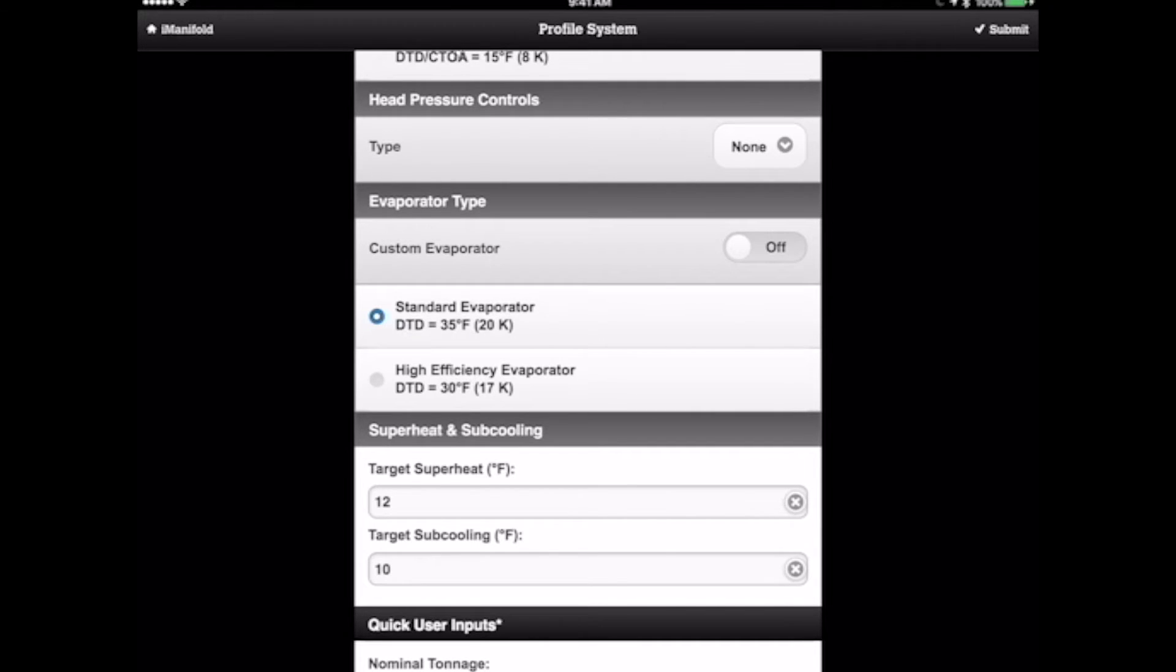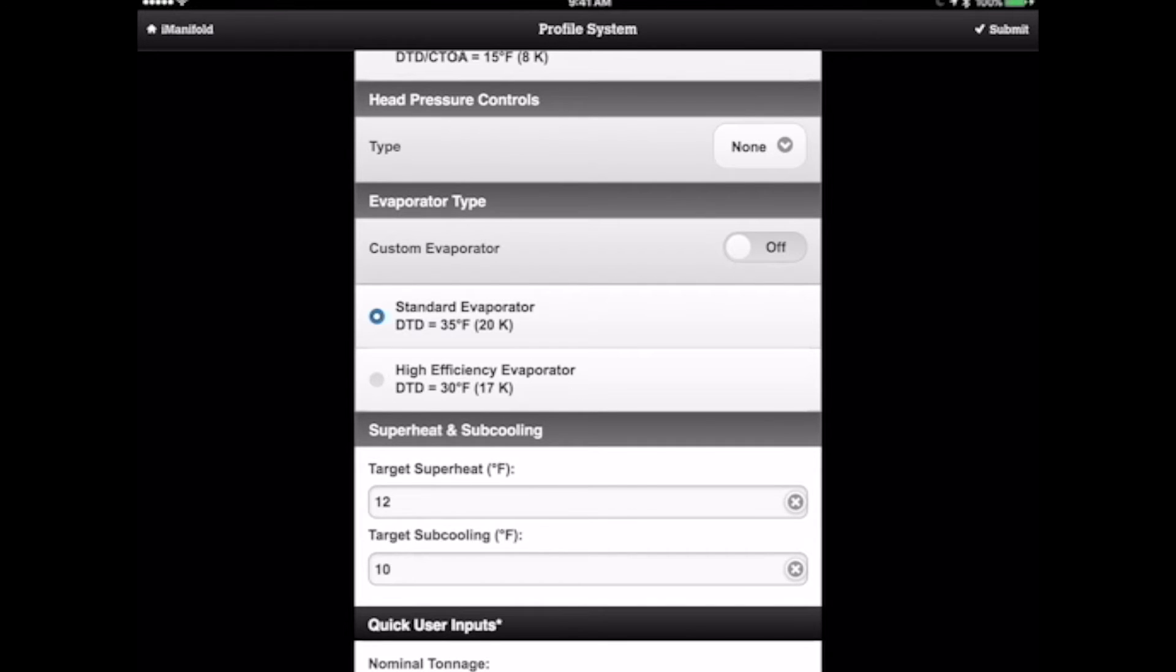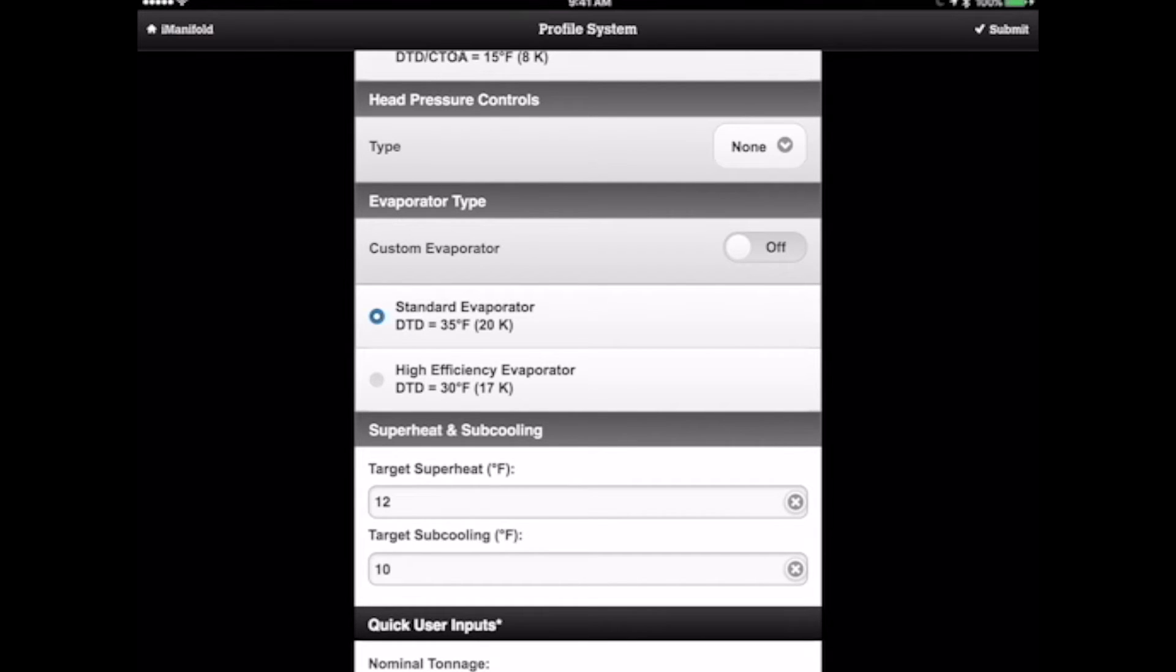The reason we know it's standard efficiency is because it's a matched system. In other words, the condenser and the air handler are matched tonnage wise - two ton condenser, two ton evaporator coil. When we get into a high efficiency evaporator, it's typically when they go a half to a full ton oversized condenser. So you might have a two ton condenser with a two and a half or three ton evaporator coil. That larger evaporator coil is going to operate at a higher saturation temperature or a lower design temperature difference.